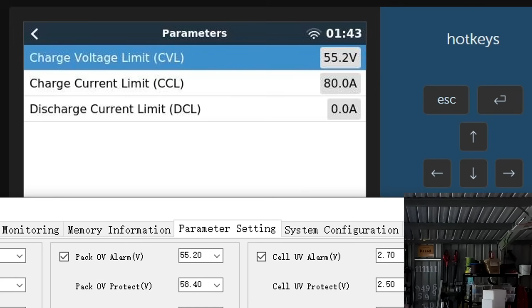And here again, it assumes the slave battery is the same size and has the same settings as the master, which is not correct. Yeah, the slave sits on 100 amp charge current. See again, no slave, no update. Read all. Write all. No update. See how inconsistent this all is? That is not good. Okay, I would say we are stopping testing here.